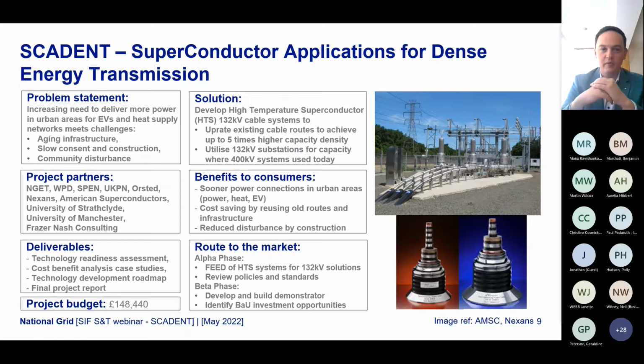Here we wanted to look at whether we can use 132 kV cable systems either to replace conventional 132 kV cables and increase capacity by 3 to 5 times, or use 132 kV technology to replace 400 kV, meaning the substation can be smaller. We don't need to use SF6 technology, we can use different insulation media, and this probably gives us more flexibility as well as cost savings on the infrastructure.